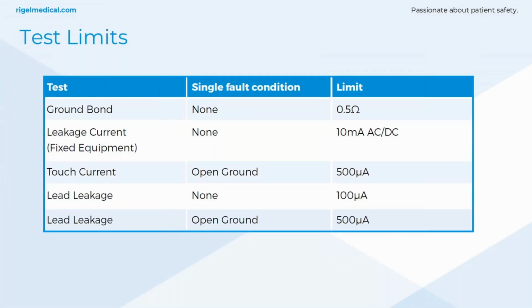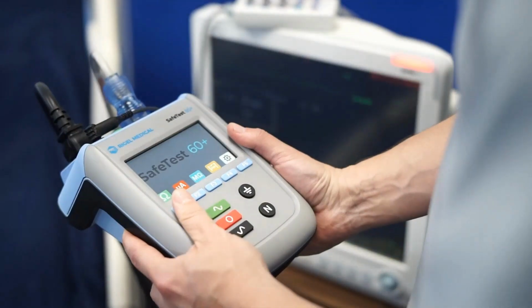So just for clarity on the tests, their limits and single fault conditions, they're there in the code, but it might be useful to have a copy. Feel free to print a copy of this. We'll send over a copy of this slide. You can stick it on the wall. It's good for a quick point of reference. But just to recap, how does this look in a sequence? I'll show you how that test is done individually. But let's run through the demo again and see how we perform that test in sequence with the 60 Plus.